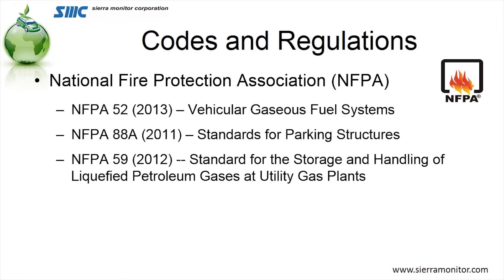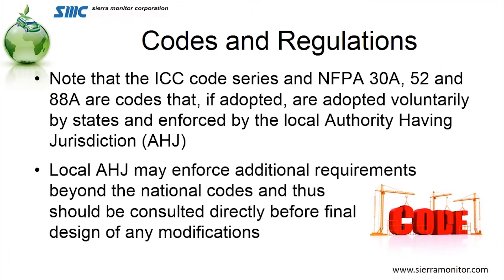Additional National Fire Protection Association codes involved in alternative fuels would be NFPA 52, the Vehicular Gas Fuel Code; NFPA 88A, which dictates what happens in a parking structure; and NFPA 59, which handles utility gases such as LPG. It's always important to note that although these are recommended code practices and ordinances, the most important thing is that unless these are adopted by the local authority having jurisdiction, they don't necessarily become law. Until the local authority has adopted them, that's when they become an ordinance or law and part of the new regulations.